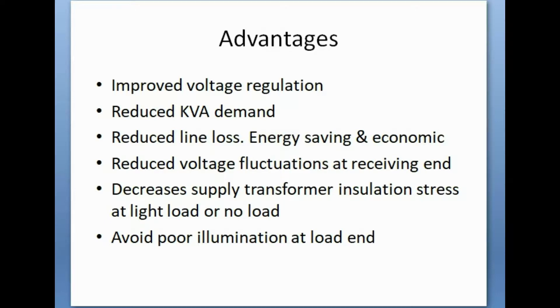This voltage fluctuation can be controlled and reduced by employing switching capacitor banks — that means controlling when to switch on the capacitor banks and how many units to switch on. It also decreases the power transformer insulation stress. At light load or no load condition during switching operations, there will be stress on the transformer insulation, reducing its life. After power factor correction, this fluctuation and insulation stress will be reduced. Additionally, this can avoid poor illumination at the load end — sometimes voltage dips occur in illumination systems, and after power factor correction this can be avoided.